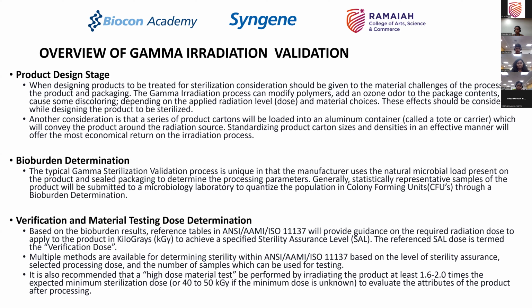This is very important. Now, the typical gamma sterilization process is unique in that the manufacturer uses the natural microbial load present on the product and sealed packaging to determine the processing parameters. So, generally, statistically representative samples of the product will be submitted to a microbiology laboratory to quantify the population of colony-forming units through bioburden determination.